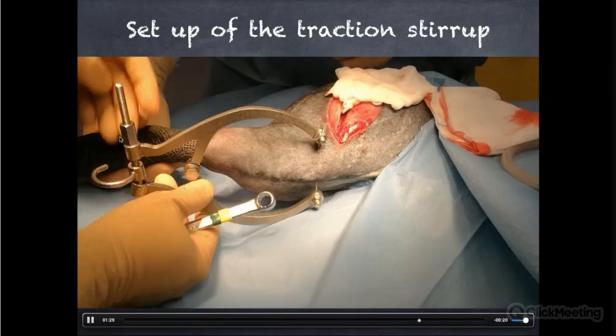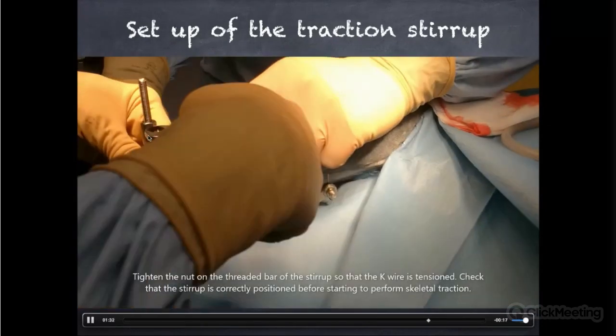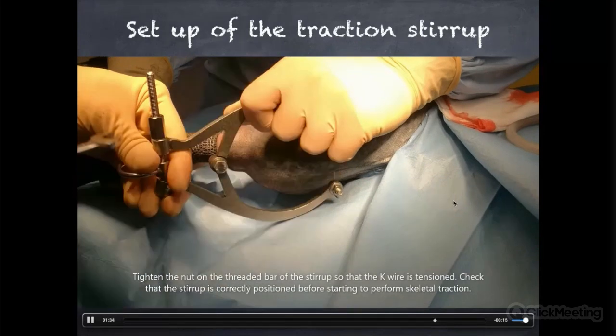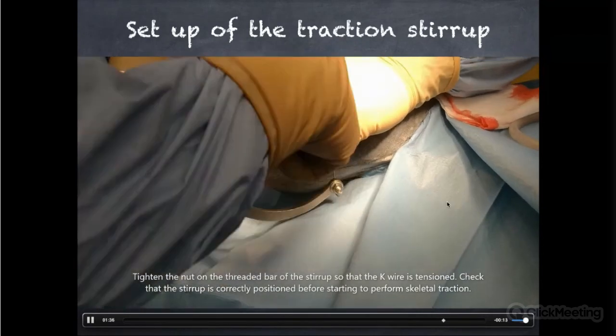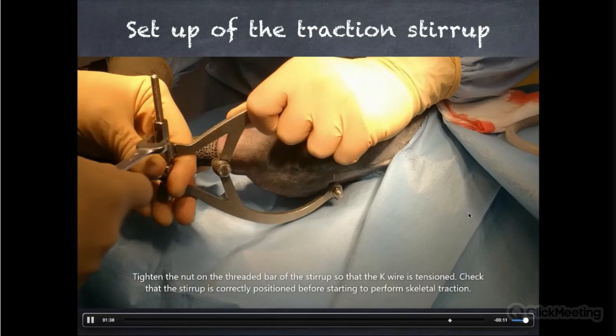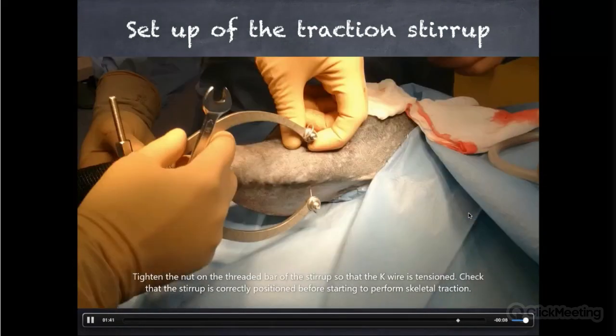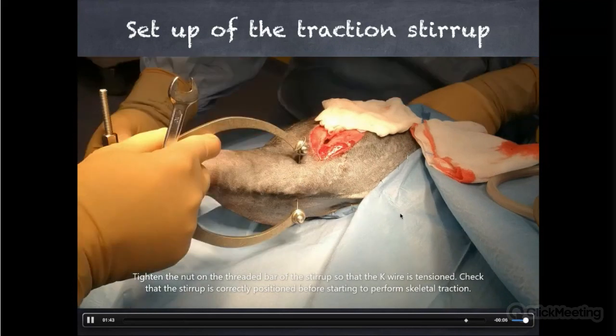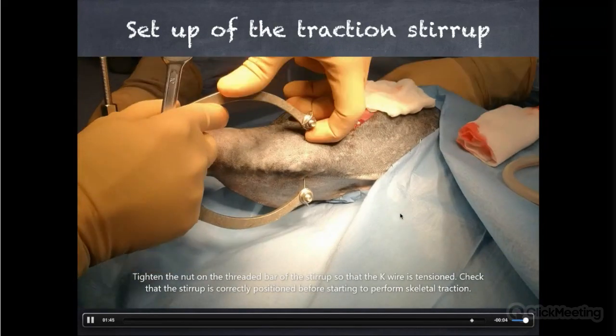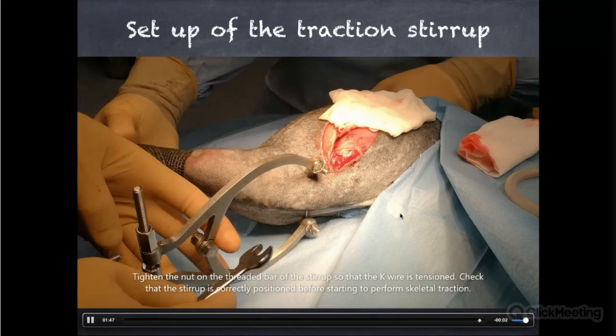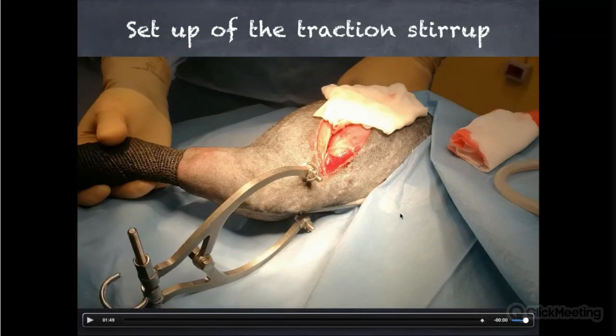And then we have this knob here that we are turning and tightening, simply because in this way we are opening the arms of the stirrup. And opening the arms means to put the K-wire under tension. I want this K-wire to be under tension, because this means that it won't bend and it won't cut through soft tissue during traction.